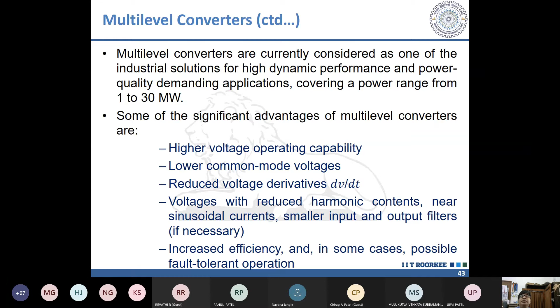So once you switch it on, in a two-level inverter the voltage swings between positive VDC and negative VDC. Once you have a 3-level, at least you have an intermediate 0. So voltage doesn't swing between the positive and the negative. Once you reach a positive voltage, you make it 0, not the negative voltage. The instantaneous current here is less, and thus the high frequency content in the inverters will be reduced.